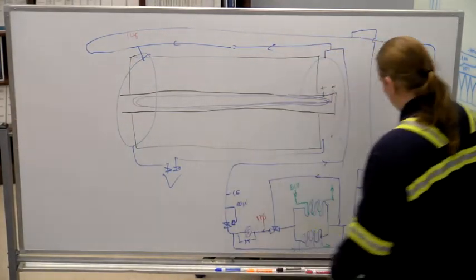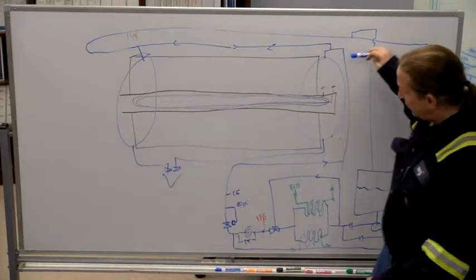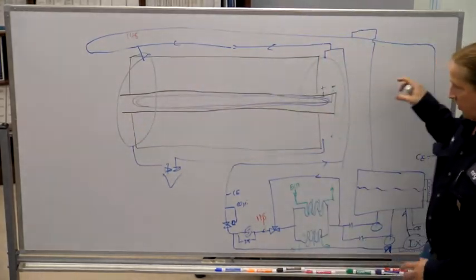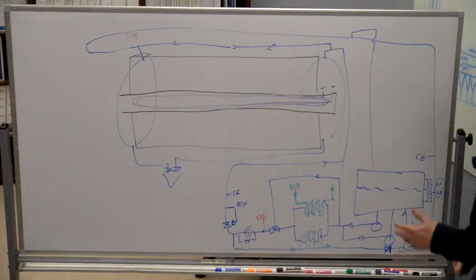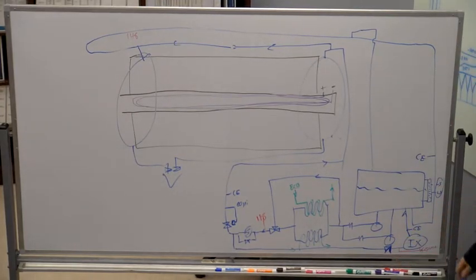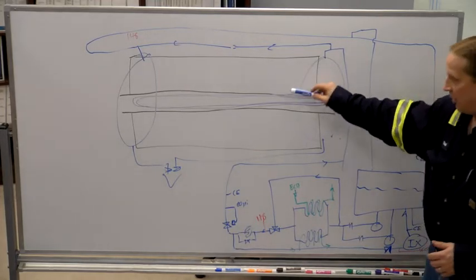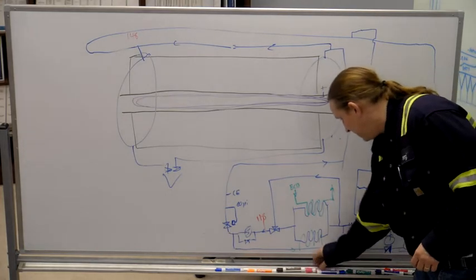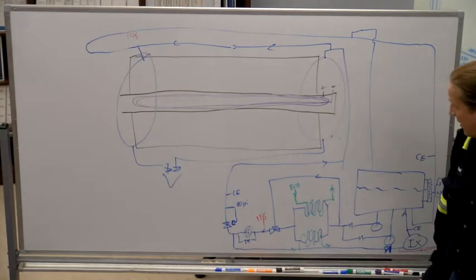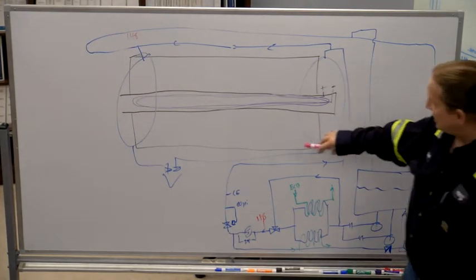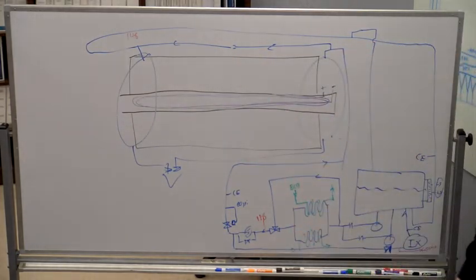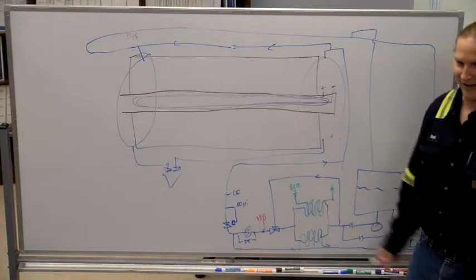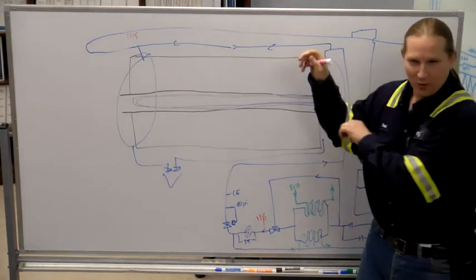Alright, so Stator Cooling Water cools the stator, which is the conducting bars for the major current of our 23,000 volts and 730 megawatts. The rotor has to also be cooled. So we do that by filling this entire vessel with hydrogen.